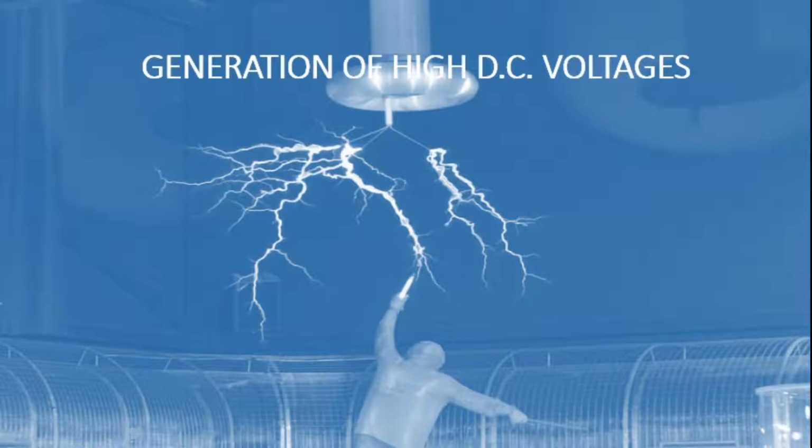electron valve type rectifiers are used and the output current is 100 milliamperes. The rectifier valves require a special type of construction for the cathode and filaments, since a high electrostatic field of several kilovolts per centimeter exists between the anode and the cathode in the non-conduction period.